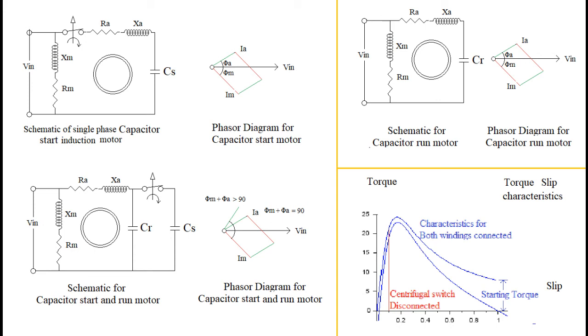The single-phase induction motor that we considered in our previous lecture was started using an auxiliary winding in combination with the main winding. This auxiliary winding is required to provide starting torque. The parameters like resistance and leakage reactance of the main winding are chosen such that the current drawn by the main winding will substantially lag behind the supply voltage.